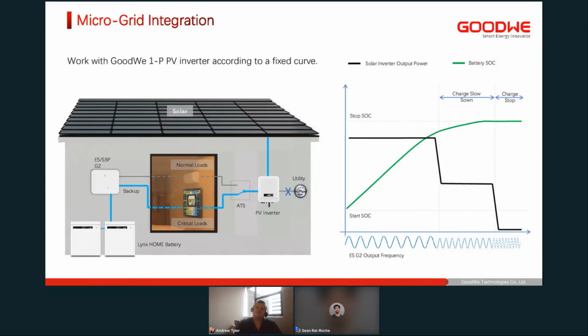What this allows you to do is to connect an ESG2 or even our S3P G2 to a grid side inverter. The grid side inverter will be connected to the backup circuits of our inverter, and via frequency shifting, the inverter is able to tell your grid side inverter how fast or slow to produce power or to charge the batteries. So you'll see on the graph on the right, we've got your SOC level, which is starting at flat and going to full. And then it also depicts the charge time slowing down or stopping completely.